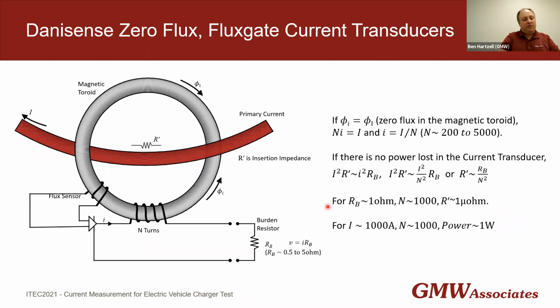If we assume a burden resistor of 1 ohm, number of turns about 1,000, then the insertion impedance is 1 micro ohm. And the next stage of that is, okay, 1 micro ohm insertion impedance, if we have 1,000 amps primary current, again, 1,000 turns, the power lost is 1 watt. And by power lost, this is the power taken out of the primary current in order to make this measurement. Compare this to a standard 50 millivolt shunt, which at 1,000 amps would have a loss of approximately 50 watts.